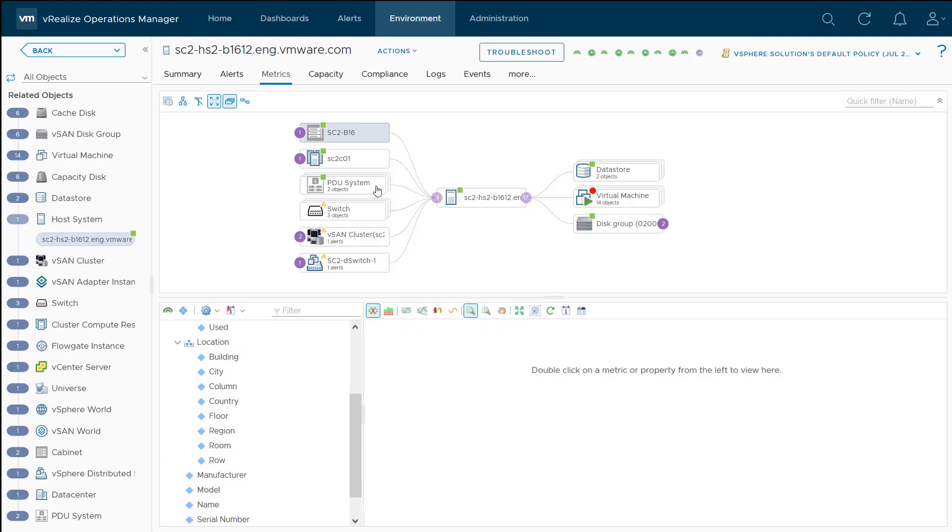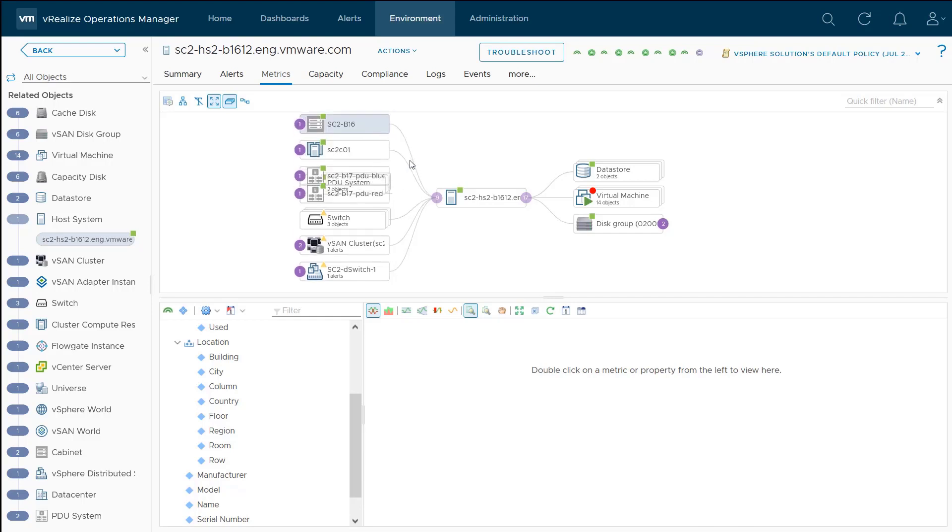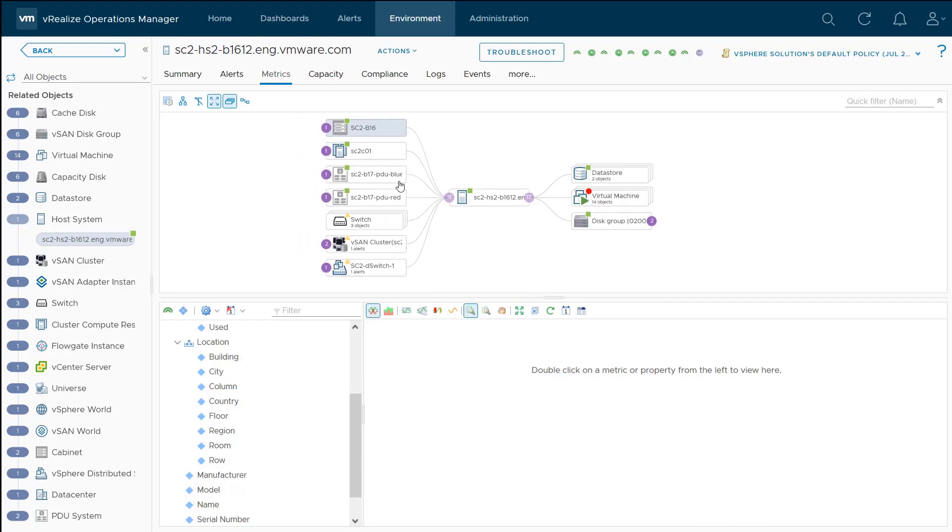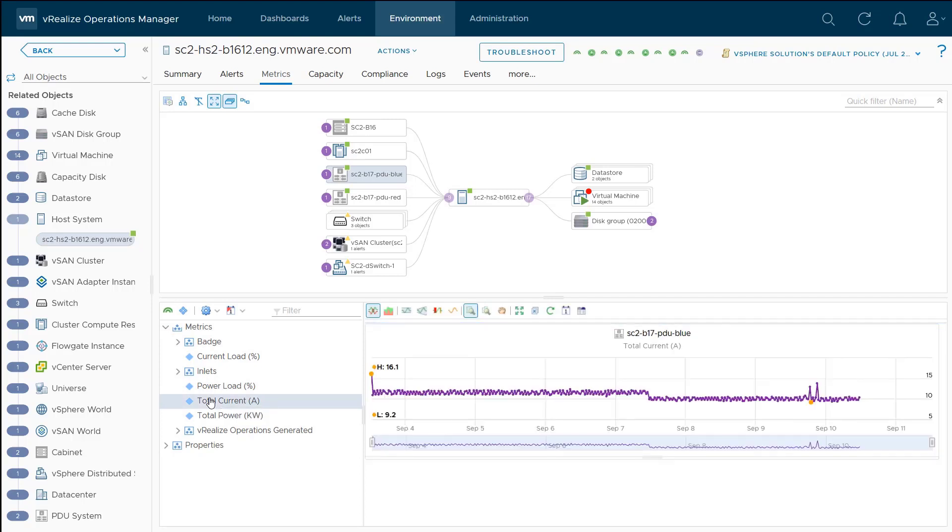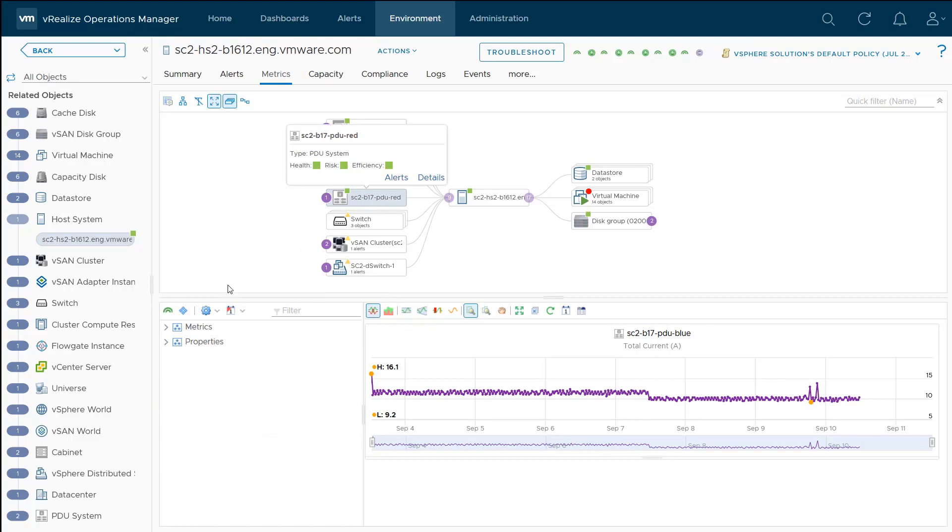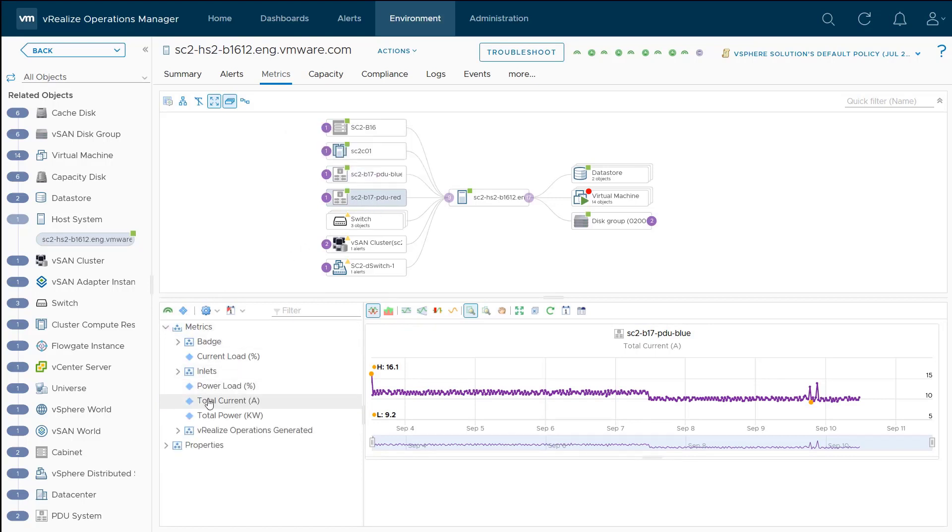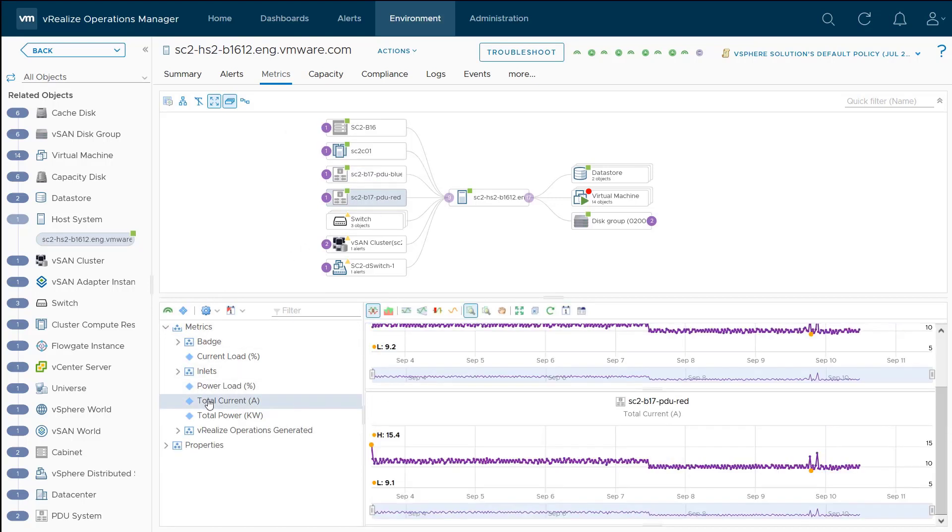If we go to our PDUs, let me expand this out, we can see both PDUs that our host is connected to. We can see metrics such as obviously power. We can look at the total current load on this particular PDU. What it can do is I can actually click on my red PDU up here, and we can look at the same metric. If I go here and go into total current, we can see that things are balanced between our two PDUs within this rack. That's pretty cool.